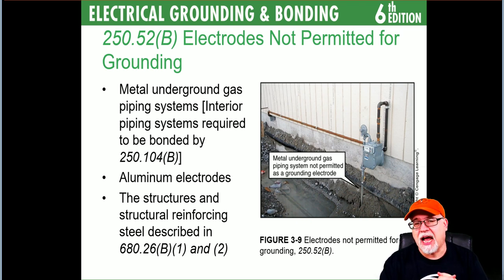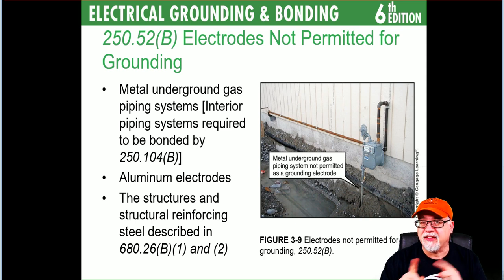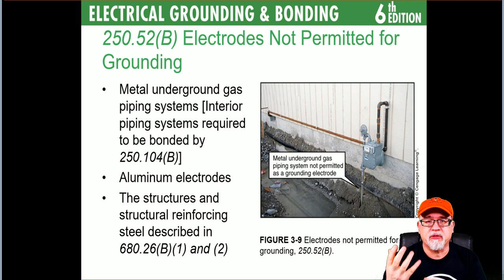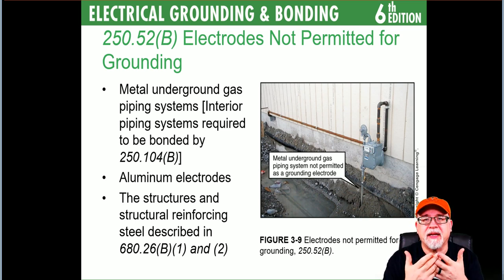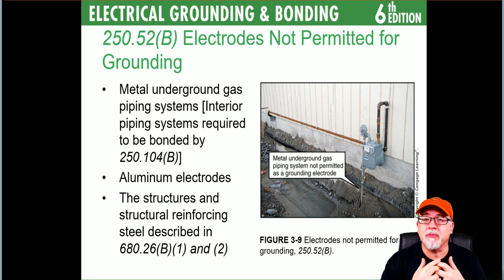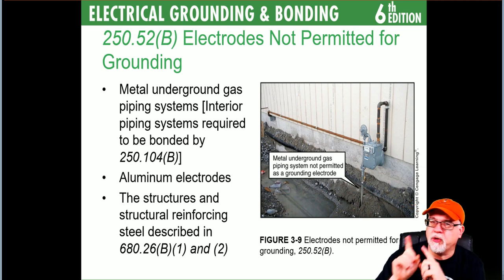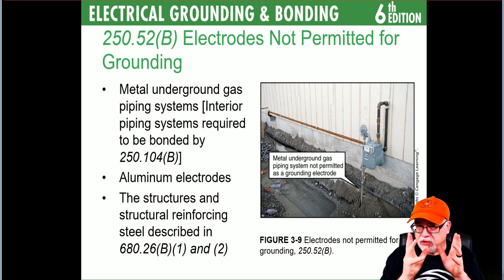There are certain things in the code that you cannot use as electrodes. An underground metal gas piping system is not to be utilized as an electrode. However, the interior piping system may be required to be bonded in accordance with 250.104(B) if it's likely to become energized — for example, where gas and electric both supply the same piece of equipment. Don't confuse bonding inside a building with electrodes — keep them separated.